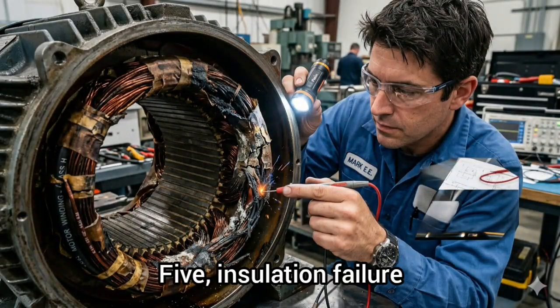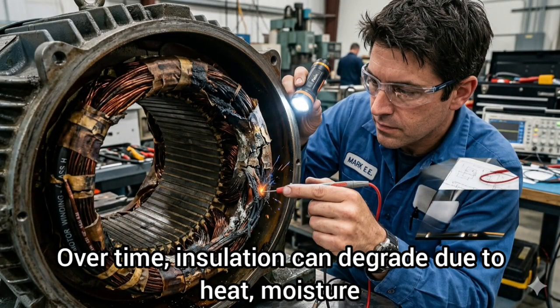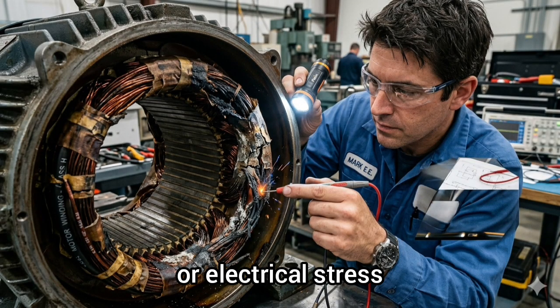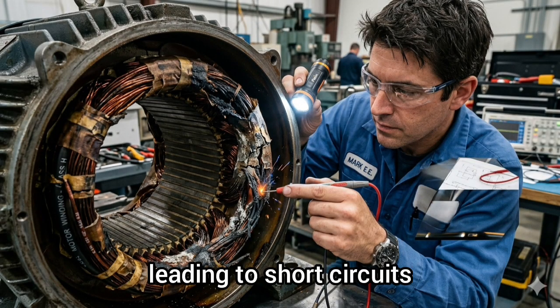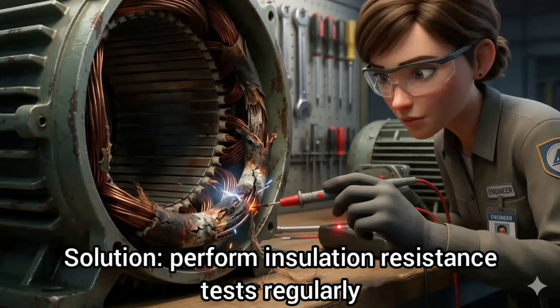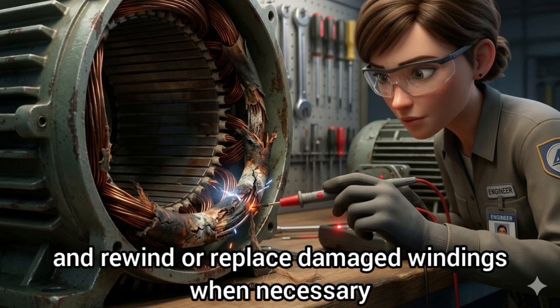5. Insulation failure. Over time, insulation can degrade due to heat, moisture, or electrical stress, leading to short circuits or earth faults. Solution: perform insulation resistance tests regularly and rewind or replace damaged windings when necessary.